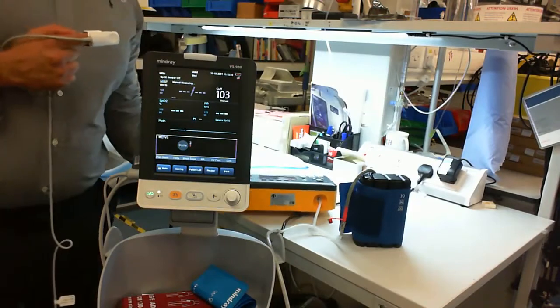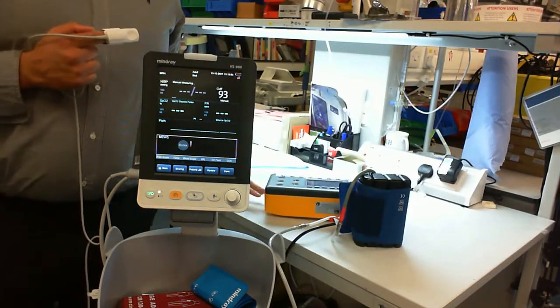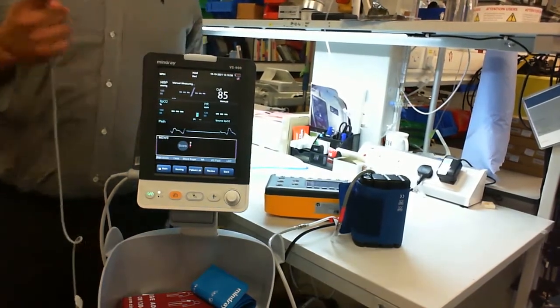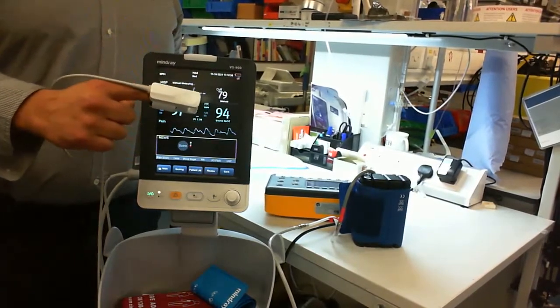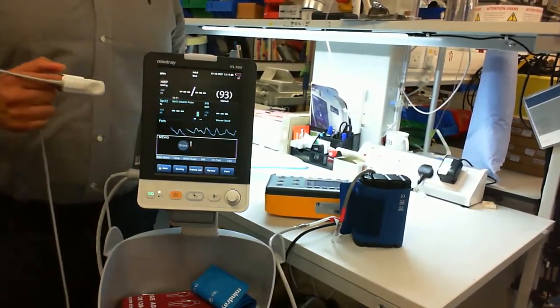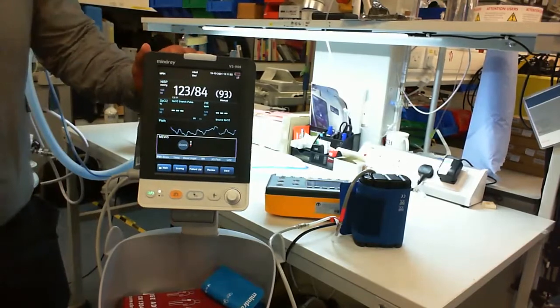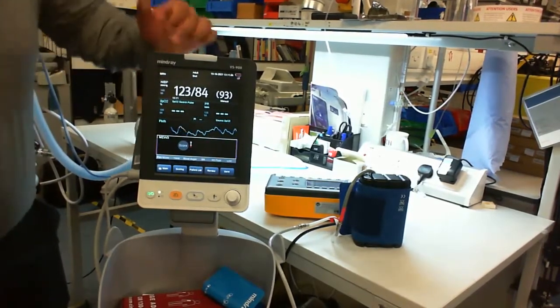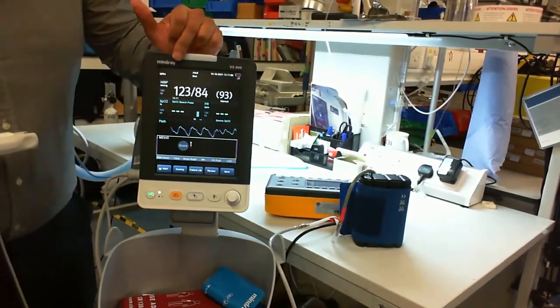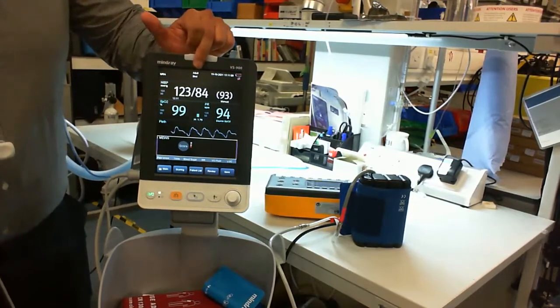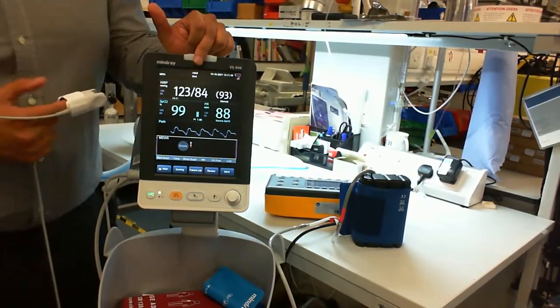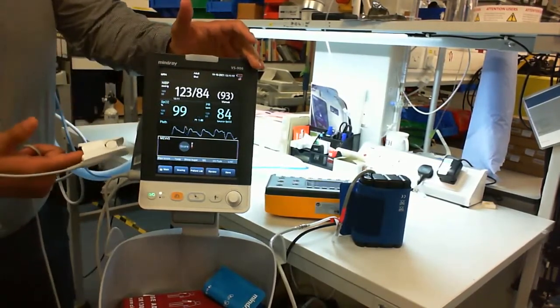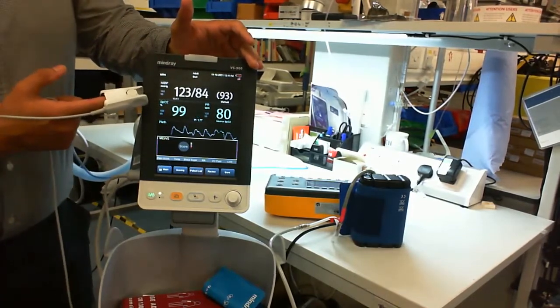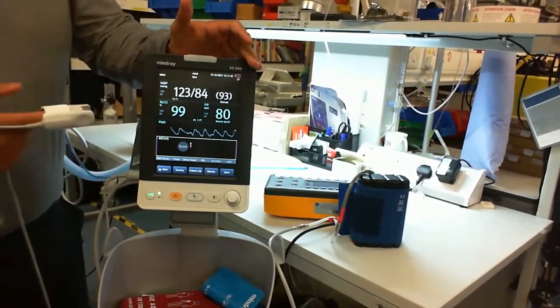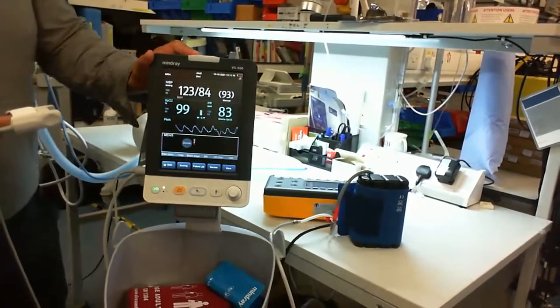We usually have an SpO2 simulator as well, but for whatever reason we've not got it on this, so I shall place it on my finger for demonstrating purposes. So that is quite a good outcome, really. It should be within range. That for us will be a pass. 120/80 is what we expected, but we've actually got 123/84. So we will actually pass that.